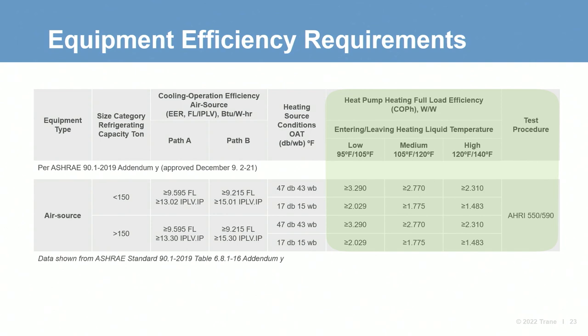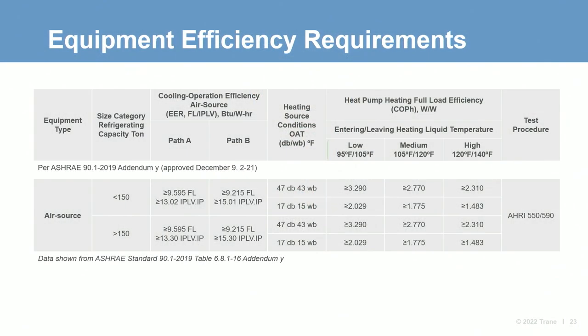For air-to-water heat pumps, the standard has defined two rating points for ambient temperature. Think of this as a mild mode and a cold mode. In order to comply with the standard, the piece of equipment being evaluated must meet the listed performance at both mild and cold heating ambient rating temperatures. With standard rating ambient temperatures defined, we now have to look at heating water temperatures. The standard has grouped these into low, medium, and high liquid temperatures. The table then defines what the minimum required COP needs to be based on the rated ambient and water temperature in order to comply. The last item to cover here is the test procedure.